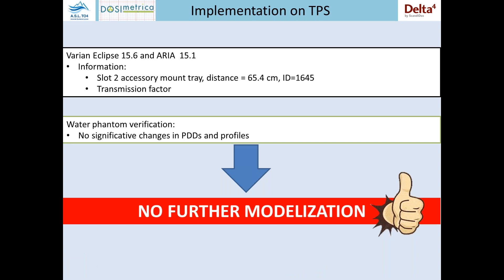The first step of our implementation was to characterize it on our TPS and in the record and verify system. We have a Varian Eclipse version 15.6 and ARIA version 15.1. In this system, it was necessary to enter only two pieces of information: the slot of the linac in which it is mounted, and the transmission factor of the detector itself. Just out of curiosity, we also performed PDD and profile measurements with the water phantom, but no significant changes were observed. So it is not necessary to create a new machine model on the TPS.